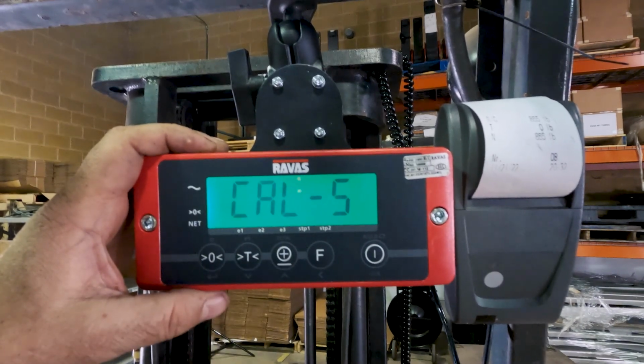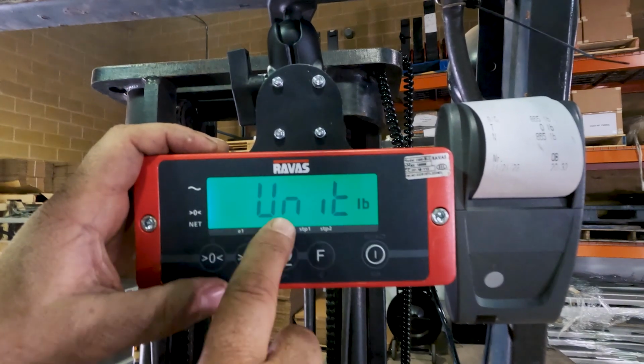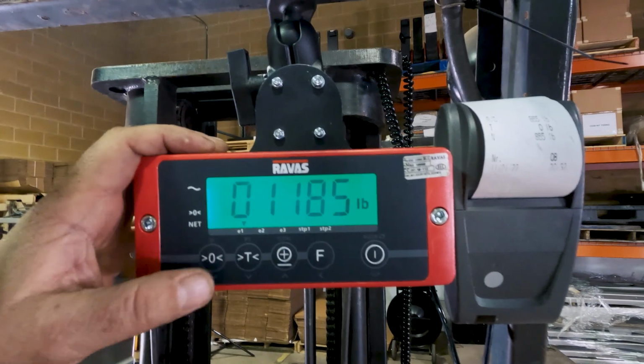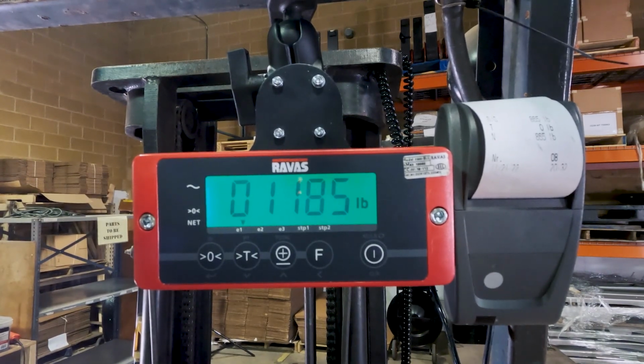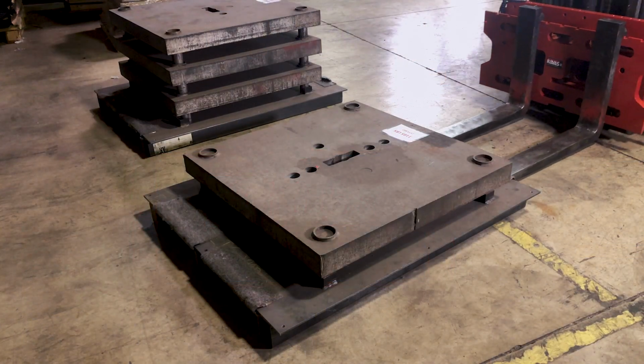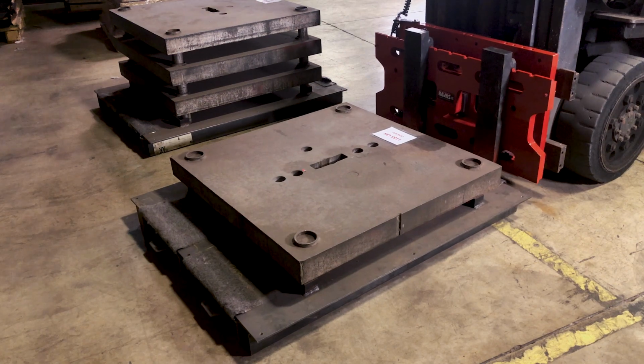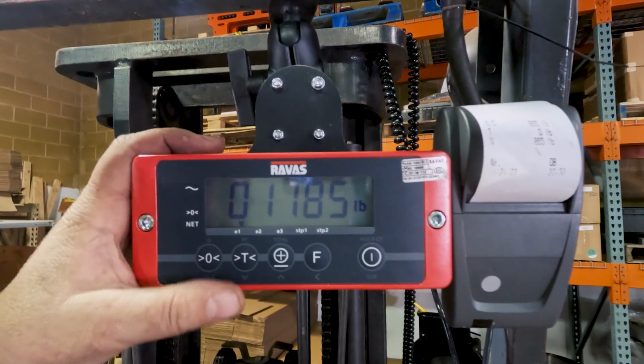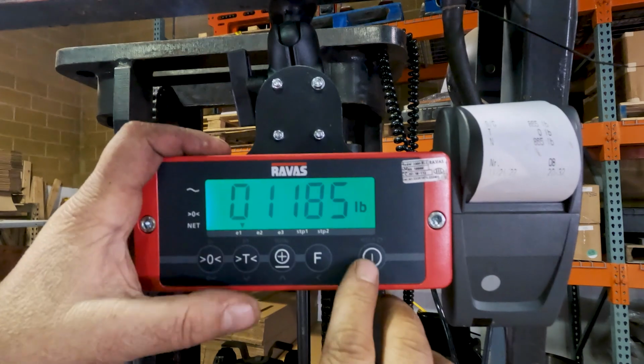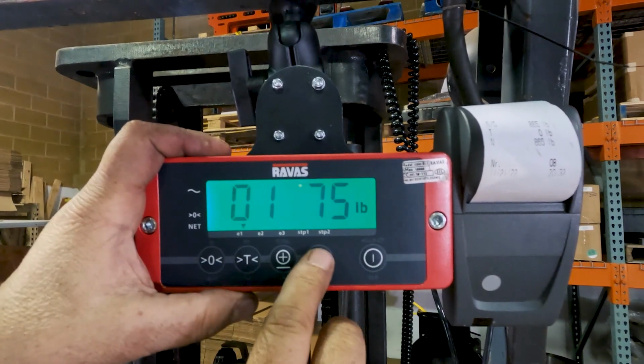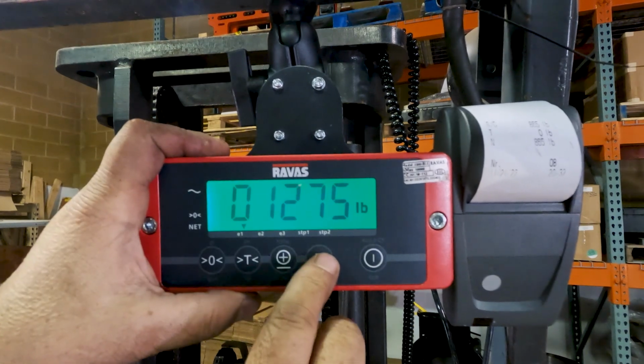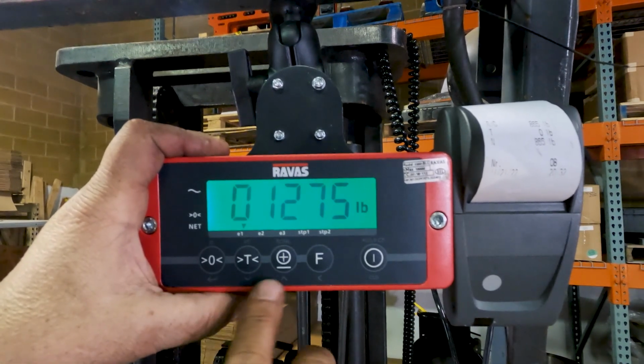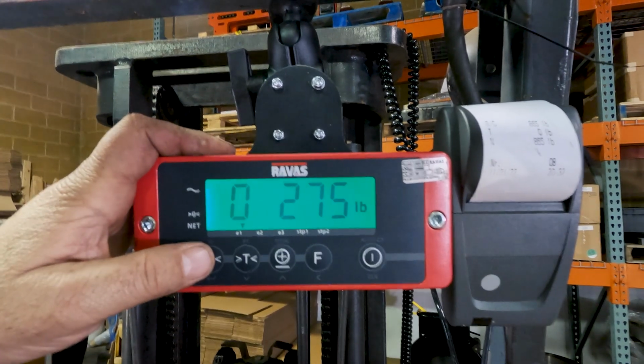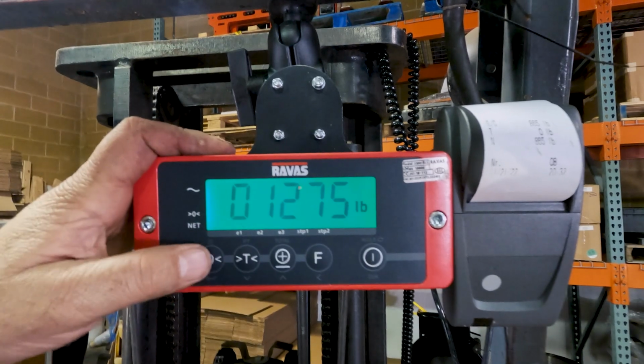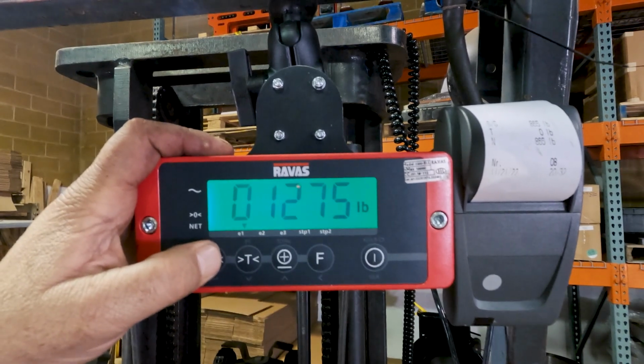Press your up arrow for cal span or cal S. Hit enter. This tells us the unit which we are measuring in, which is pounds. Hit enter. We will now proceed to pick up our weight. We're now going to hit the enter button, moving the cursor to the left, and enter our known good weight. Using our arrows, which is down, up, left, we're then going to press the enter button when the weight is entered. With E1 flashing, we're going to press and hold the enter button until it says adjust.